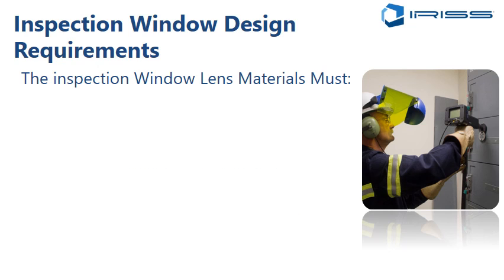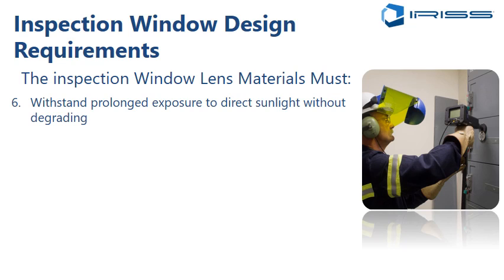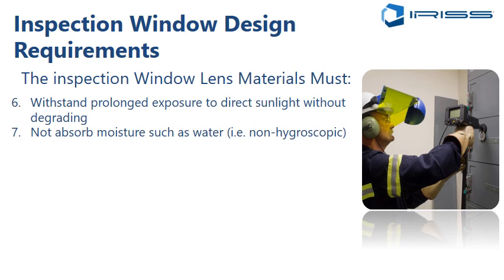The inspection window lens must also withstand prolonged exposure to direct sunlight without degrading. Not absorb moisture such as water, so as we do know that fluoride based crystals are hygroscopic and they will absorb water over time, water, acids and alkalis, the humidity, and that will degrade the lens system. So again, you don't want anything that's hygroscopic.